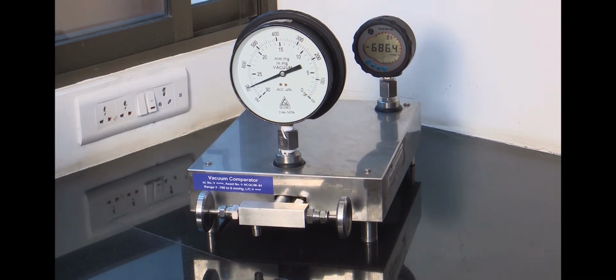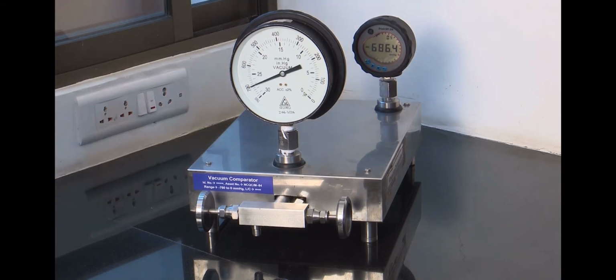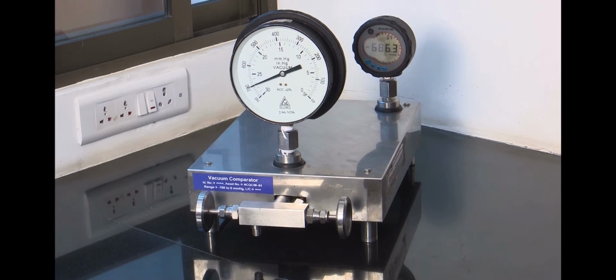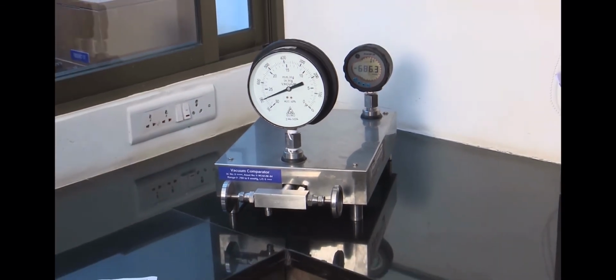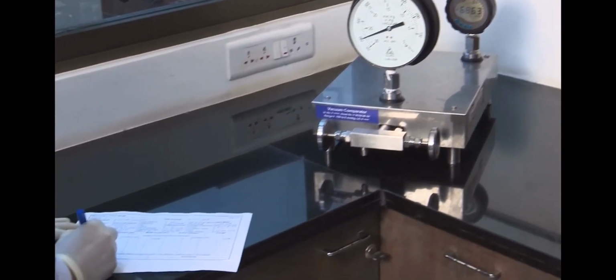Decrease the pressure on UUC and set it at -700 mm Hg. Allow it to stabilize for 30 seconds. Now record the reference standard reading in the worksheet.